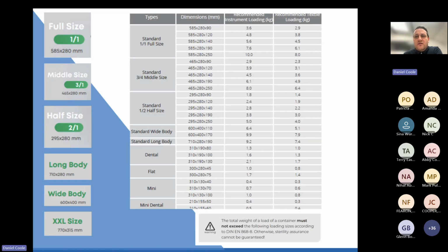The dimensions are quite relevant when you're looking at containers and moving to containers, if it's something you're considering. The reason being, of course, you're restricted. The container is the size that it is. If you have a set that won't fit in that size basket, if you're used to having a double DIN basket, then it's likely that you're going to have to duplicate those and have double the amount of baskets, or double the amount of containers that you'll need.